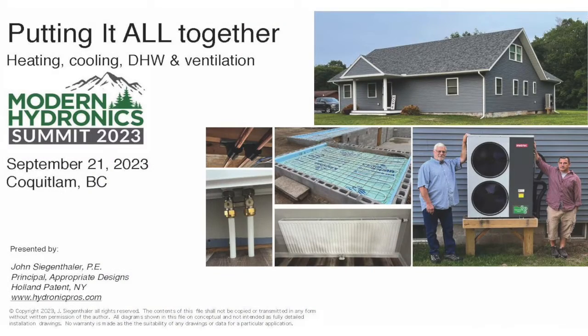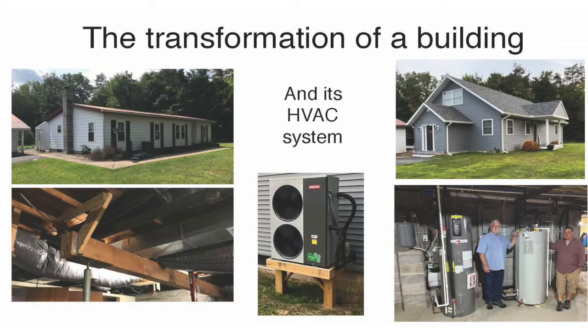and that is heated with an air-to-water heat pump. It is doing panel radiators. I mentioned this morning we had a project with panel radiators operating at about 90-degree water temperature. And I'll show you the schematic, and you'll see how basically we've pulled together space heating, cooling, domestic water heating, and heat recovery ventilation, pulled it all together in one system. The transformation of a building and its HVAC system.